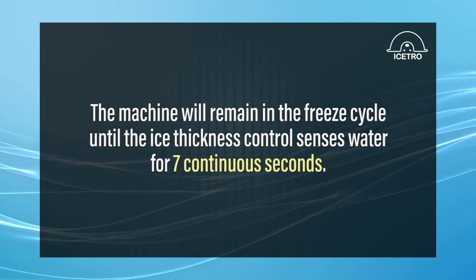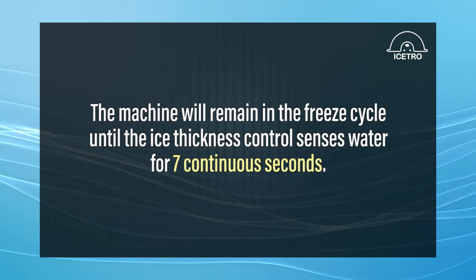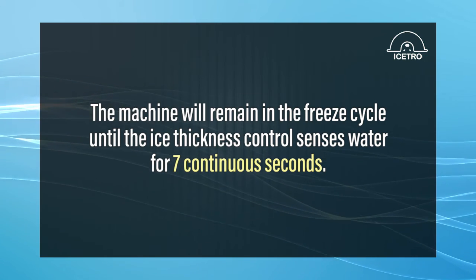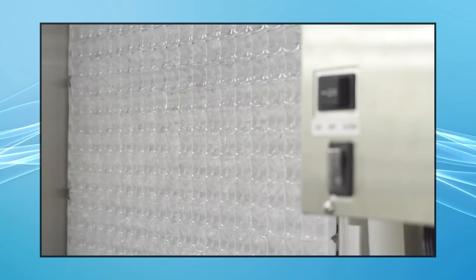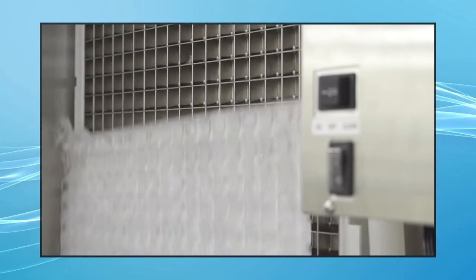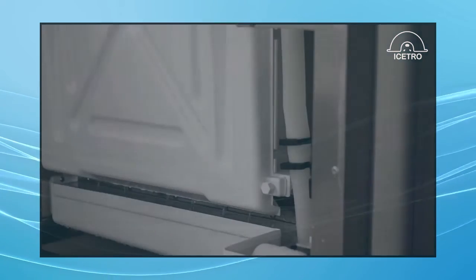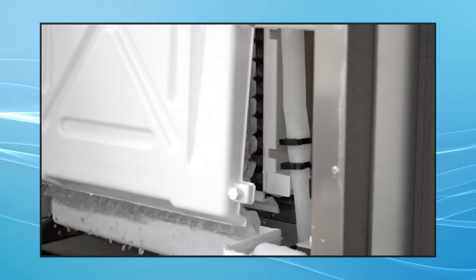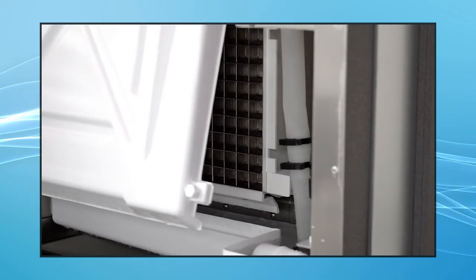The machine will remain in the freeze cycle until the ice thickness control senses water for seven continuous seconds, then it will initiate harvest. The machine stays in harvest until the ice clears the evaporator, falls into the bin, and causes the curtain switch to open and close.